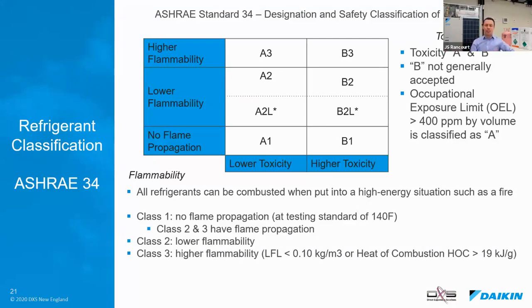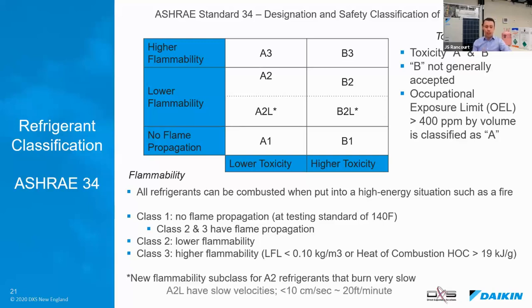And the way that we separate those, there's a lower flammability, class two, and a higher flammability, class three. And what we look at is the lower flammability limit, the LFL of a refrigerant. What that means is how much of that refrigerant, what concentration would I need in this room for the refrigerant to sustain a flame? And if you don't need much, that's a dangerous refrigerant. Therefore, it becomes a class three refrigerant. The heat of combustion is also something we look at. Now, the recent topic, not so recent, but is there's a new subclass for A2L refrigerants that burn very slowly. It is called the A2L or the 2L category. So if a refrigerant is an A2, but the velocity of a sustained flame is less than 10 centimeters per second, that's about 20 feet per minute, if you imagine how fast that is. It is categorized as a 2L refrigerant.